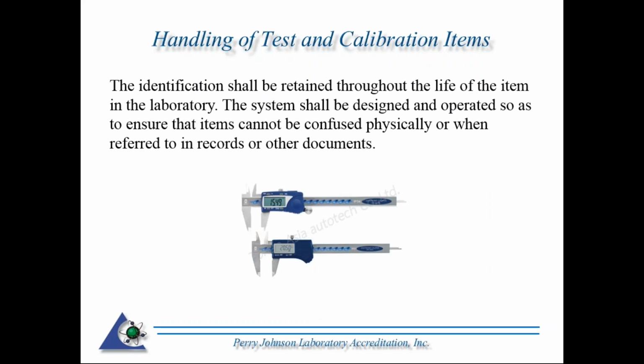The identification shall be retained throughout the life of the item in the laboratory. The system shall be designed and operated so as to ensure that items cannot be confused physically or when referred to records or other documents. Hence, items in the picture down here are two exact same types of calipers. You have to be able to differentiate one from the other, even if it was the same customer client that submitted these calipers. Each one has to have some sort of unique numbering, unique identification.